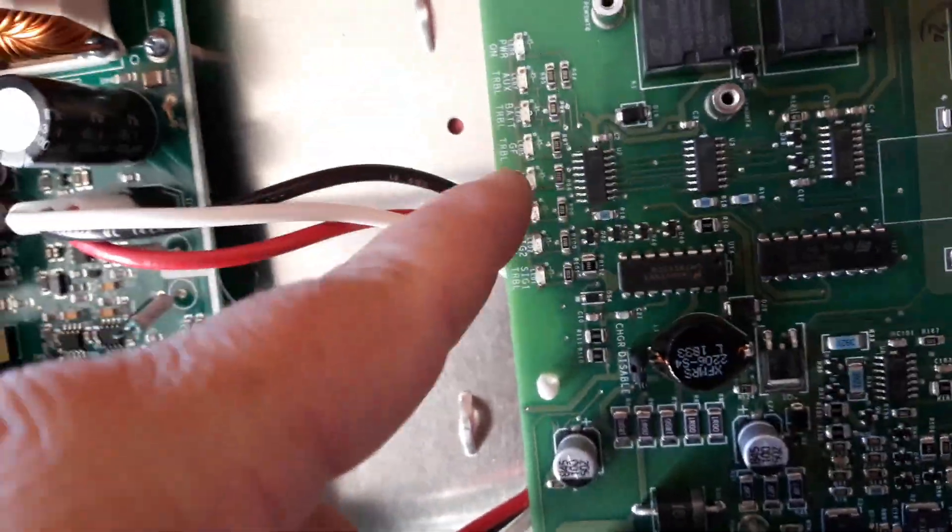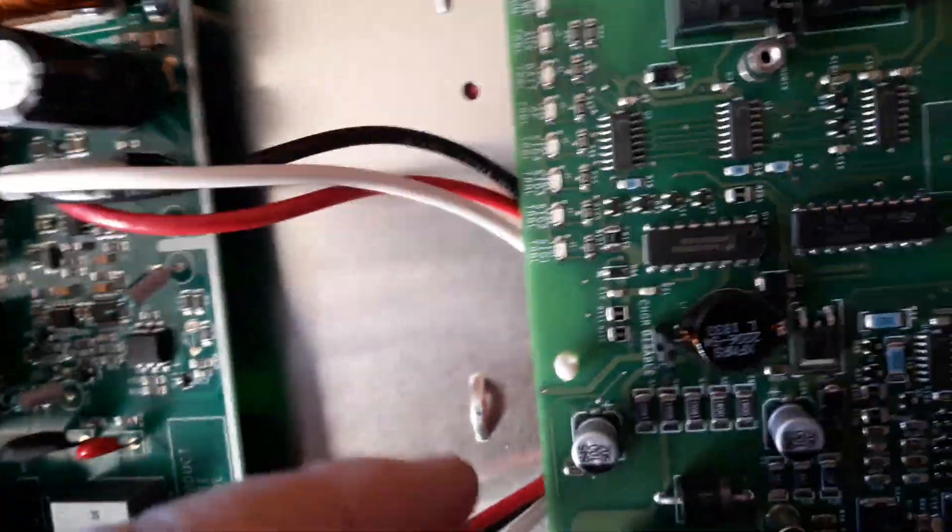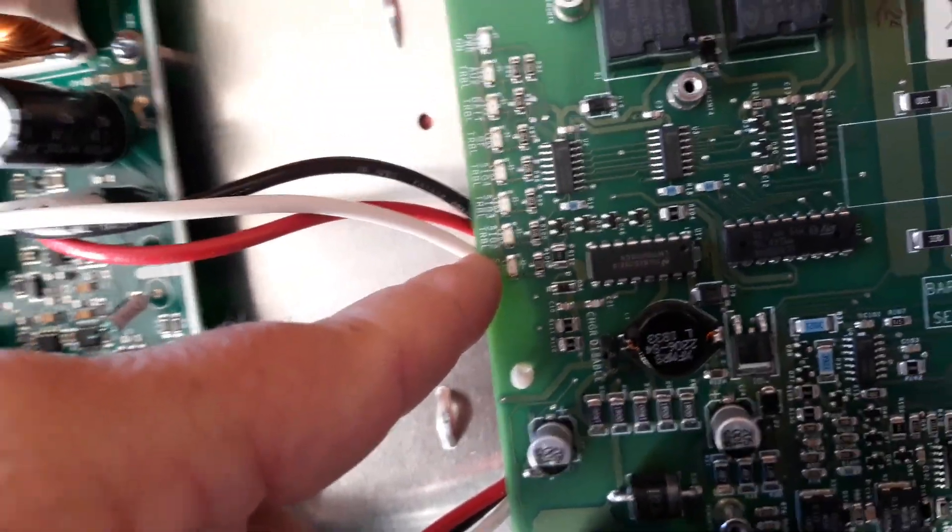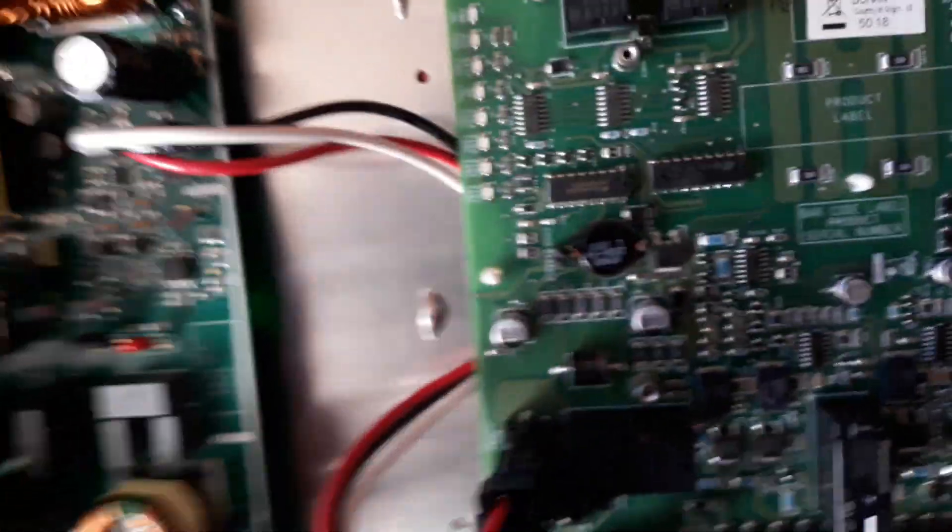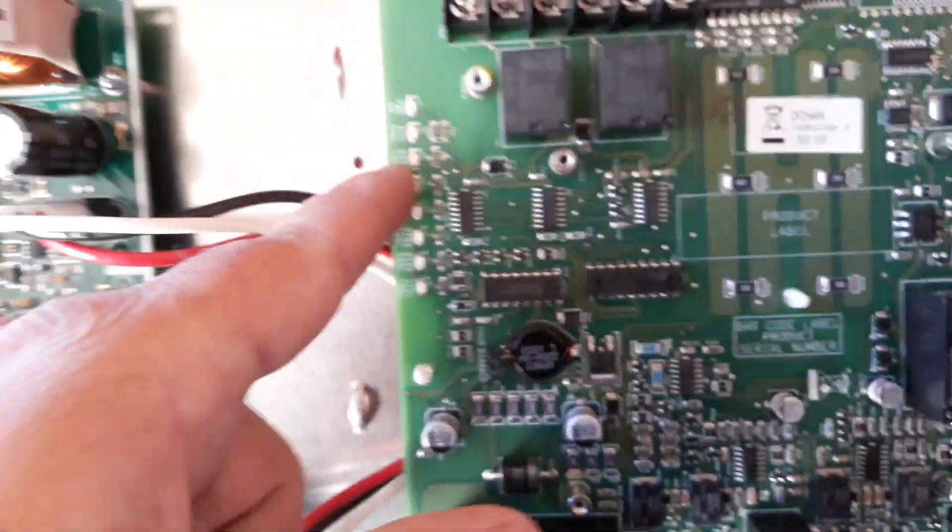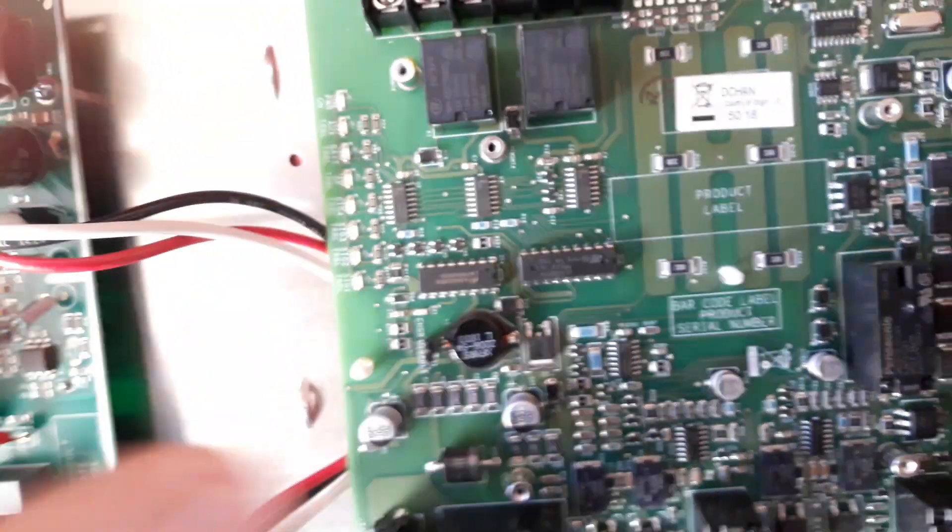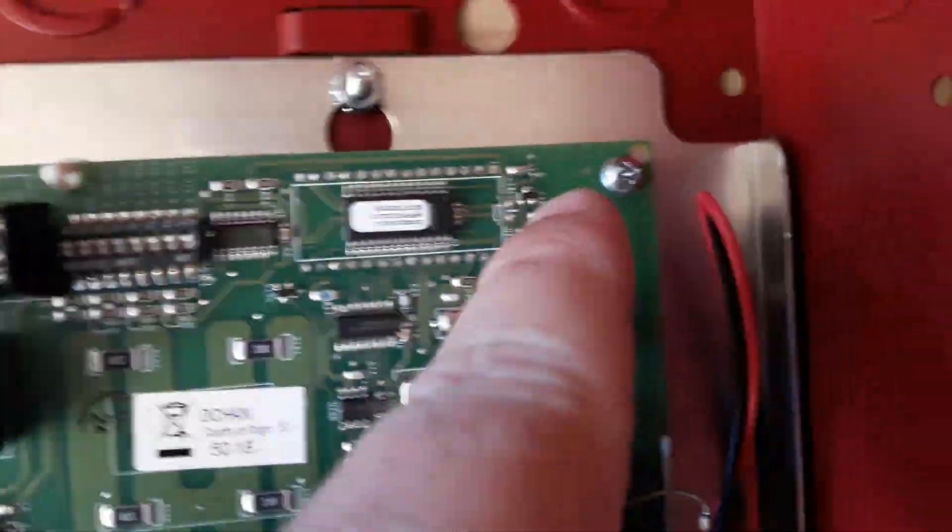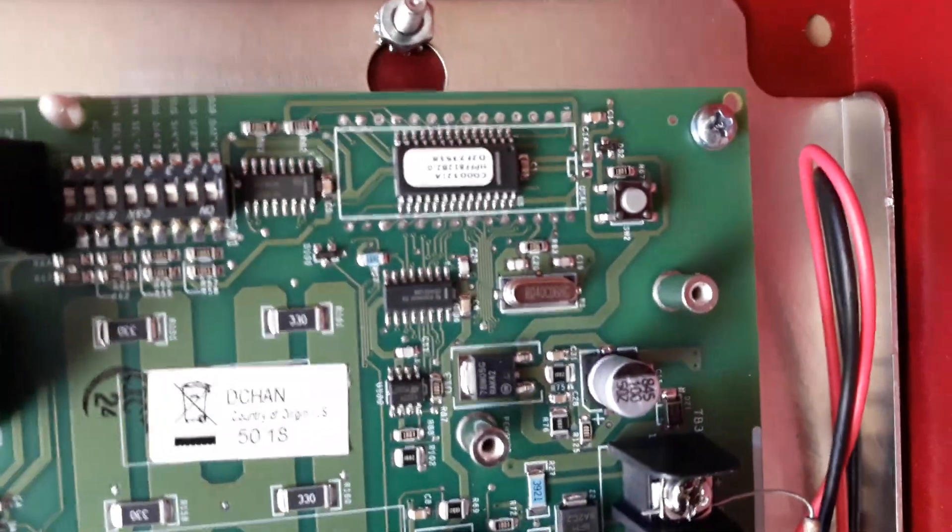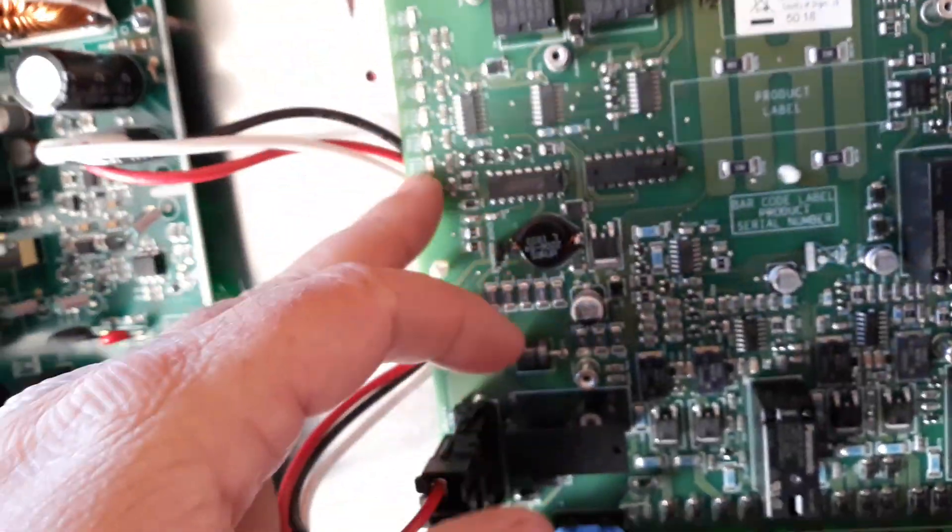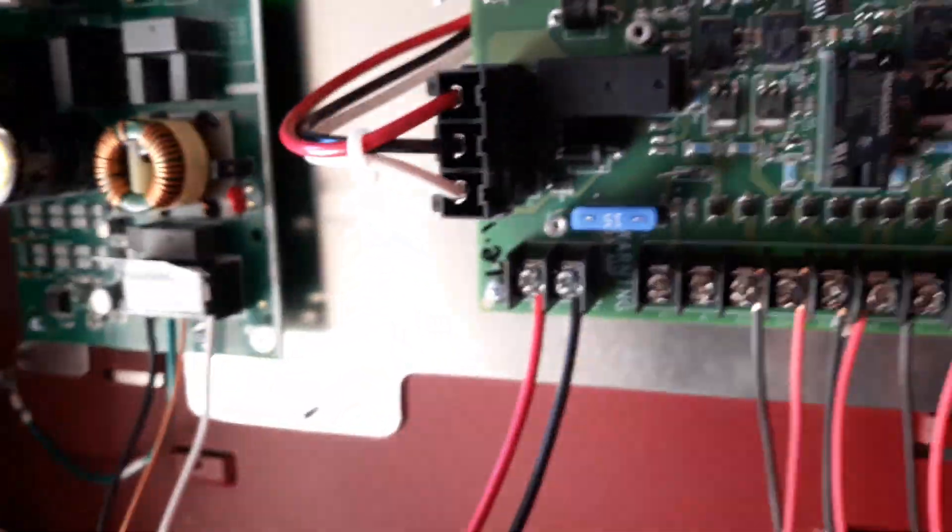But a lot of panels don't do that. They'll just go back to being normal and don't blink and let you know which one it was. So you think, well what do you do to clear that completely out? So what I do every time after I'm troubleshooting on it and I'm done troubleshooting, I'm going to reach up here and hit the reset button. That little reset button will clear this and reset the panel itself.